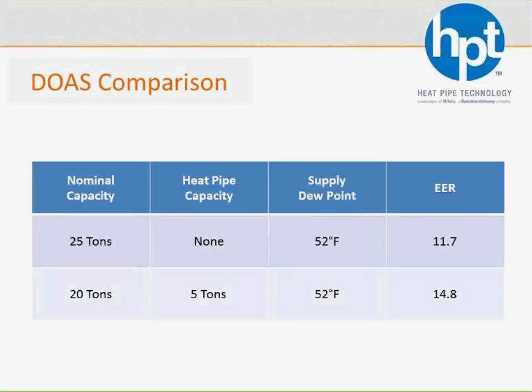The one before has got hot gas reheat. We're providing free reheat on the wraparound side. We're getting the same dew point, but now not only have we reduced your capacity obviously by 20%, so we've made the unit smaller, it's going to weigh less, but more importantly, it's going to be more efficient. And you can see right there we increased that efficiency by about 25% because it takes a lot less energy to overcome the little bit of static pressure that we add to the system.